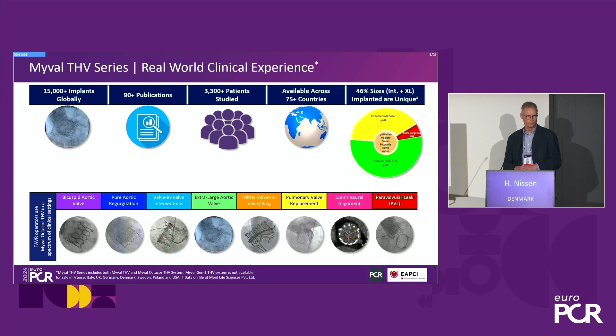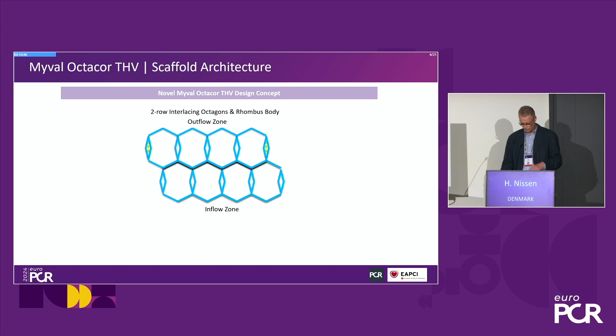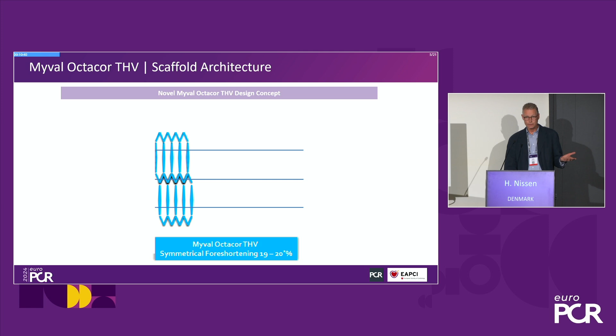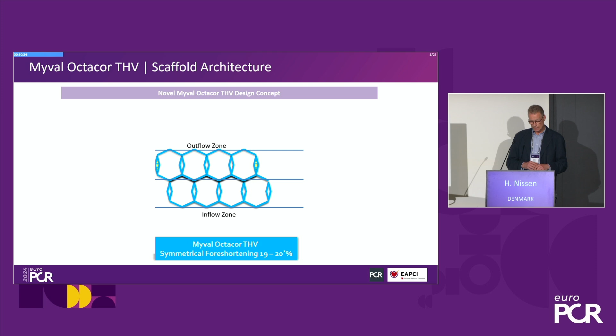It's been used, of course, in all the IFU cases, but also, as you see below, in all these off-label cases where we are forced to use TAVI valves occasionally. It's called Octacor due to this octagonal design with two identical rows, the upper row in the outflow zone and the lower in the inflow zone, with overlapping parts which give this rhombus body and support the valve in the longitudinal force. It is quite unique in that, due to this design with identical cells, it expands completely in a controlled fashion, identically from top to bottom, with shortening of only 19 to 20%, which gives quite good confidence when you're implanting the valve.